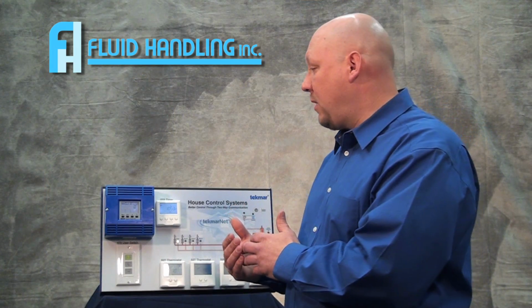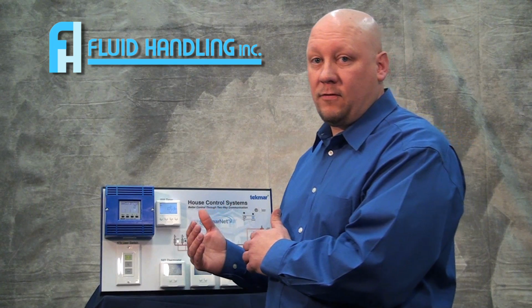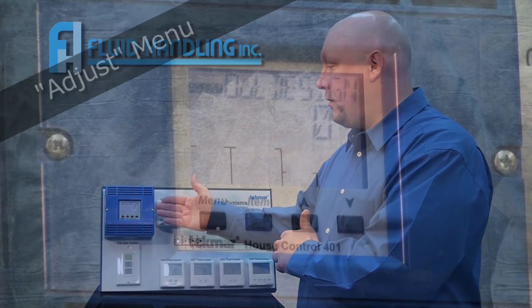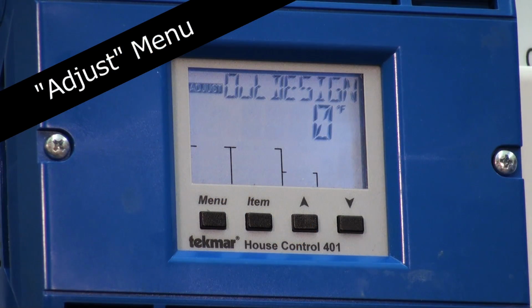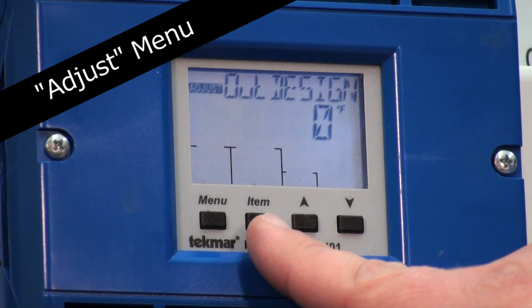Here's where you're going to set up the parameters based on the design of your HVAC system. Outdoor design temperature is the design temperature that you have designed your HVAC system at. If you are designing in our area here in Wisconsin, Milwaukee area, you're -10. You get up north by Green Bay and north, you're going to be looking at -15. Go even further, you could be -20. So you need to find out from your designer where he set it. That's going to be your setting here.